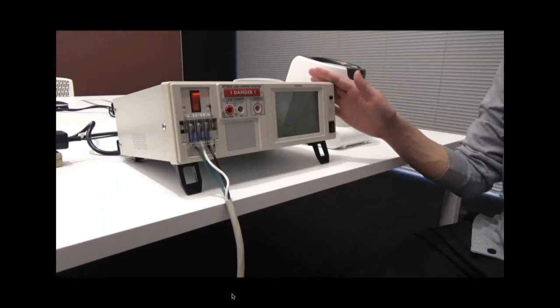I'm going to explain the general operation of the ST5540 leakage current tester. This instrument is designed to measure leakage current, especially those which could flow through the human body. The instrument incorporates various measurement network models which simulate the electrical resistance of the human body. The ST5540 measures leakage current using these simulated resistance networks. This includes measurement networks used not only for medical equipment, but also for general household appliances or general equipment.